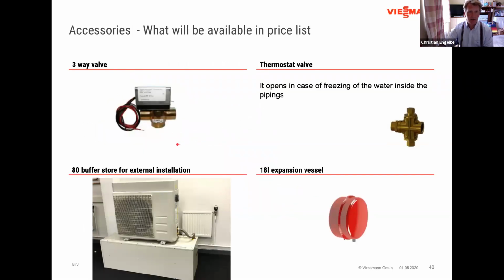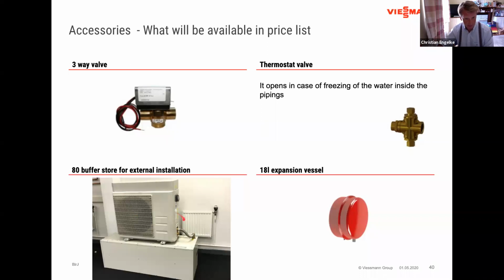Then what accessories do we have available? Obviously the 3-port valve, which I'll show you in the schematic diagram a bit later. That's for switching between hot water mode and space heating mode. We do have an attractive option there for an external buffer storage. That can also be used as a plinth, so the outdoor unit can actually be mounted on top of the buffer store outside of the property. Ideal for space-saving installations where inside the property there's not enough space for additional buffers. I discussed last time the requirement for buffers, and when it's required to have buffers in place. So that is certainly an option to minimize any space requirements.